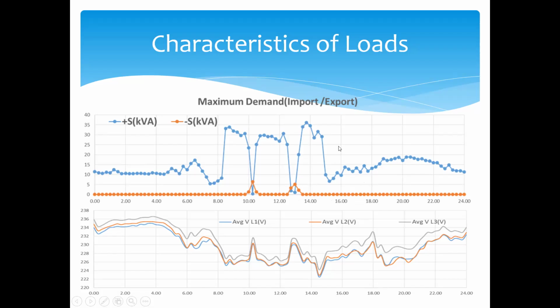Then I came to know that this transformer is supplying a small factory that carries out production using coconut shells. So this is their tea time and this one is their lunch time. Once they switch off their machines, due to the installed rooftop solar, it changes from import to export mode only during these time intervals. You can see the voltage also increases during those two occasions. Otherwise it has low voltages in the feeders.